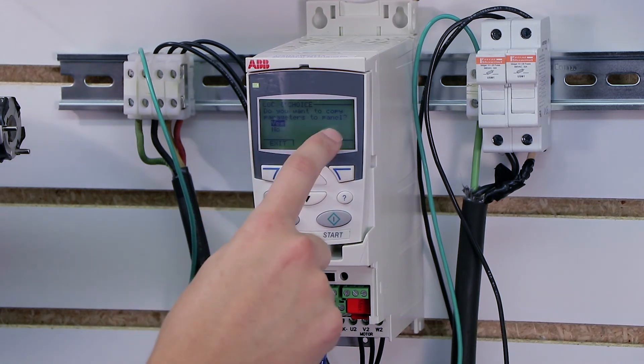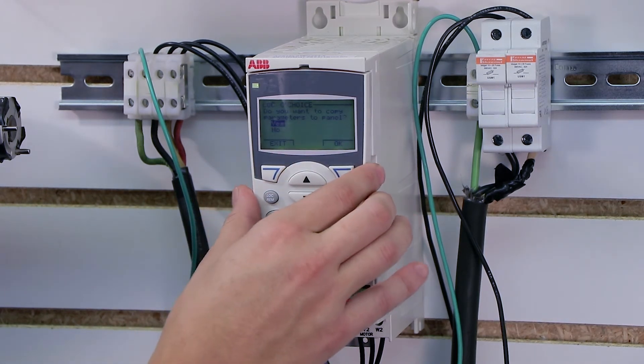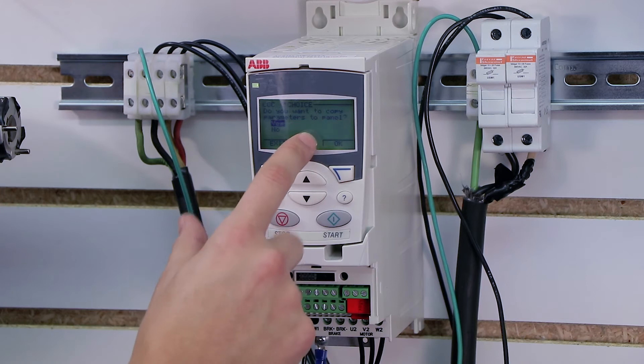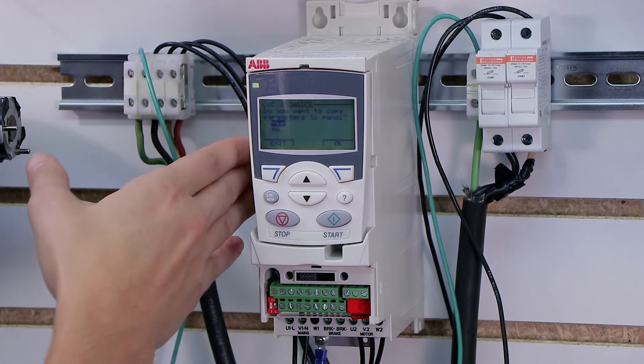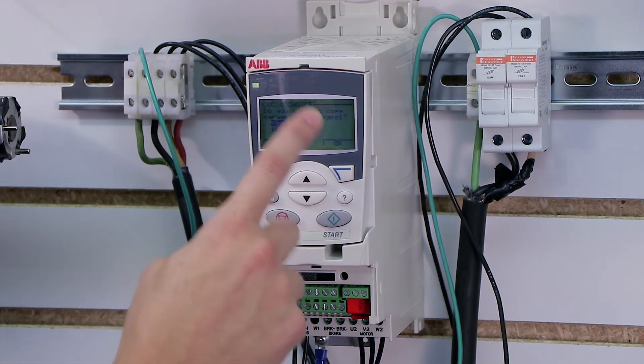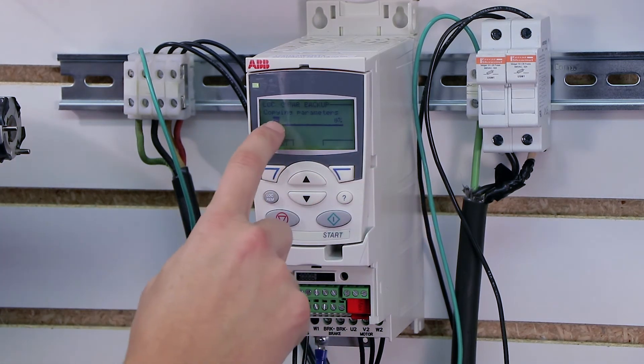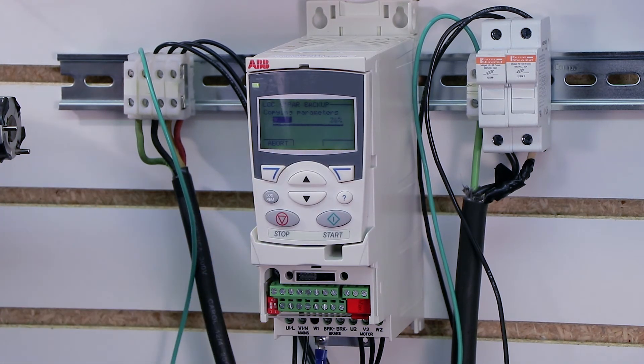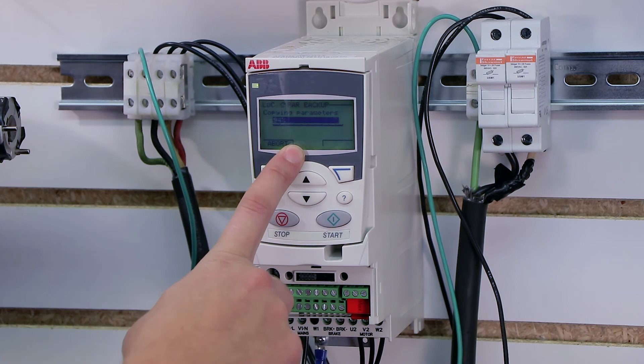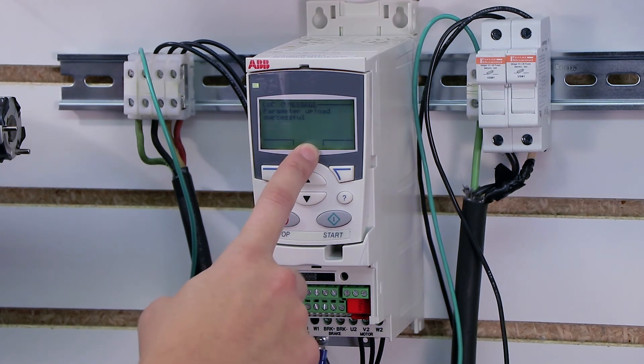Do you want to copy parameters to panel? Now this is kind of nice. It'll actually back up your program to the keypad. So if your drive ever fails, you can actually pull this keypad off, put it on a new drive and load it into it. So we're going to say yes. And you'll notice as a progress bar that scrolls across. And that is really all there is to the basic startup and commissioning of the ACS355 through the keypad.